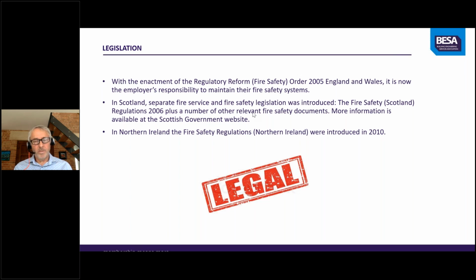One thing to note with all these reforms, safety orders and regulations is, for clarification, there is no exception to complying with any requirement under the fire safety order. There's no risk-based assessment that can remove the requirement to test fire and smoke dampers annually as a minimum. All of these documents state that fire and smoke dampers have to be tested at a minimum every 12 months, and I know that's not happening at the moment.